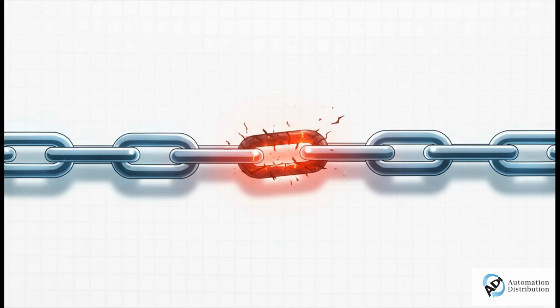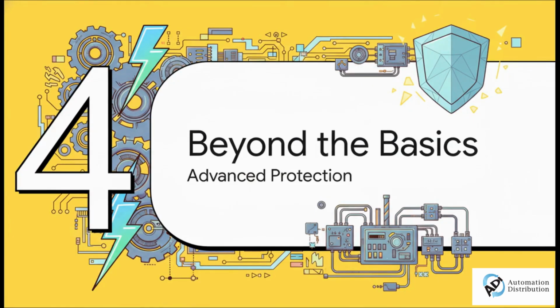So if you have this huge main breaker rated for 65,000 amps, but it's feeding a little terminal block that's only rated for 5,000 amps, guess what? Your entire panel's official rating, its short circuit current rating, or SCCR, is just 5,000 amps. That's a fundamental rule you just cannot ignore. All right, so that 6-step plan we just talked about, that's your foundation. It covers the absolute must-haves for every single panel. But some applications have unique challenges that demand more specialized strategies. Let's take a quick look at a few of those.